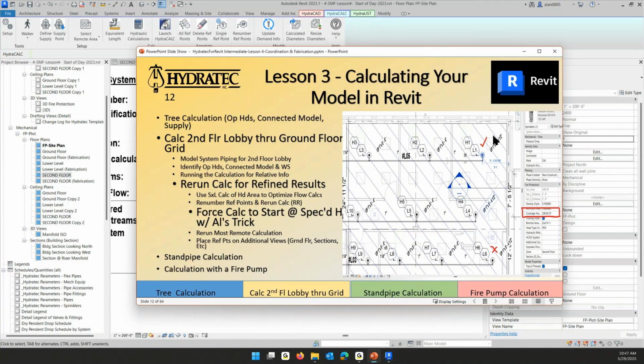I think by accident I'm getting that because this one's 169 square feet and none of the others are more than 169 square feet. That probably makes this the most remote. But my trick, if all things are equal, is to simply make that have a really big remote area till I get the calc opened and then put it back.